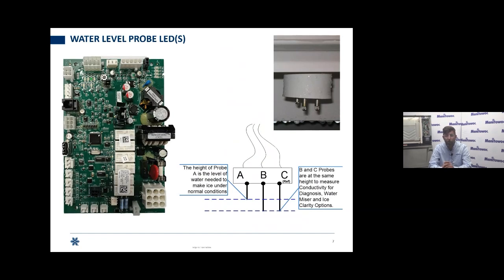Remember that this is a 3-prong probe. You've got 2 long sticks and a short stick. The 2 long ones are going to be your low and your common probe, and the short one's going to be the high. As the water starts to rise, it's going to touch the 2 longer sticks first, and the LED that you see lit up now will light up, letting you know that the low probe is satisfied. It's there to measure conductivity for diagnosis and for our water settings.